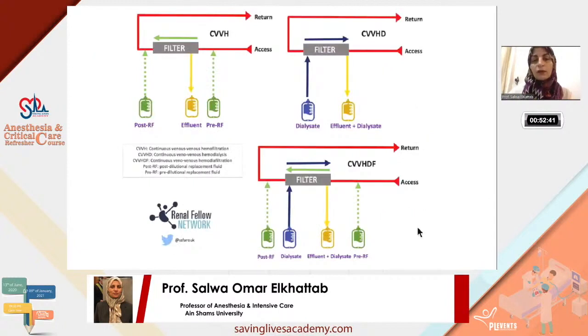And this is the diagram showing three modalities, one with only replacement fluid, where we are getting out fluid together with some solutes, and the replacement is either pre- or post-dilutional, pre-filter or post-filter.